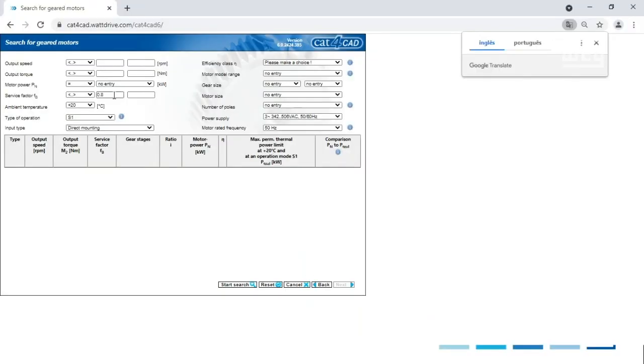Okay, here we are going to input the main data from the application. So output speed, if you have this data, we consider here 30 to 50. If you have the output torque available as well, you can consider it. If you don't have it at this moment, you can leave it. So motor power, if you have this information, we are going to consider here 1.1 kilowatt. There are other fields that can be completed here as well, okay? For the energy efficiency class, in this case, this is about the motor. I'm going to consider IE3.